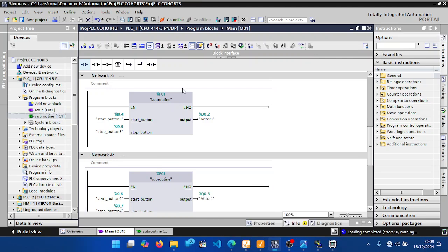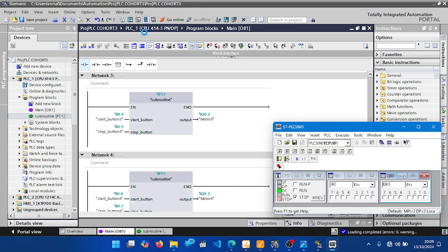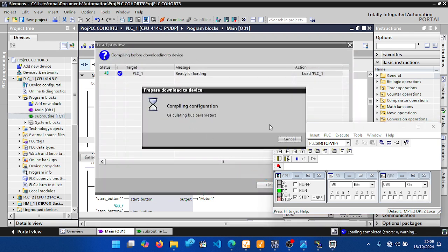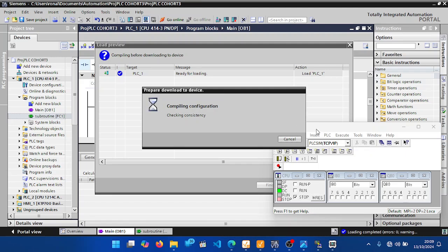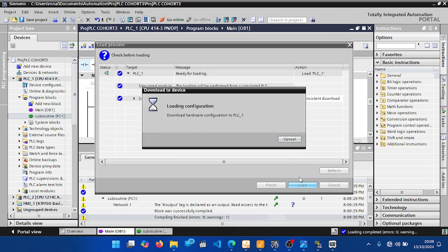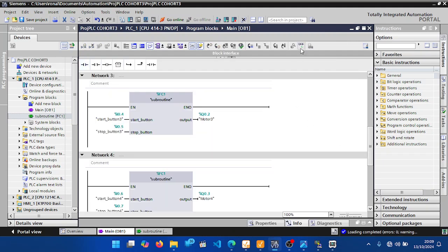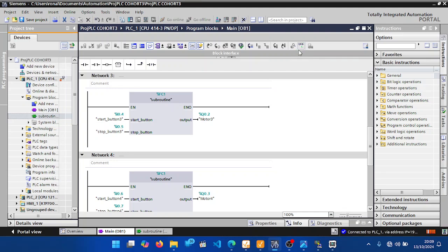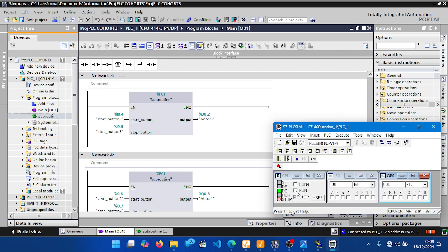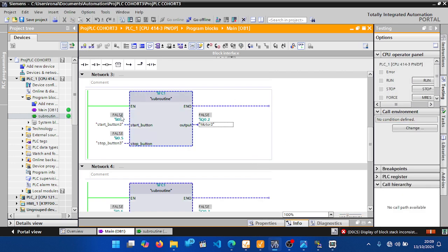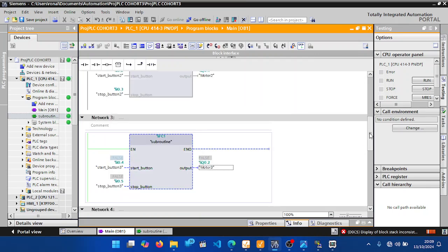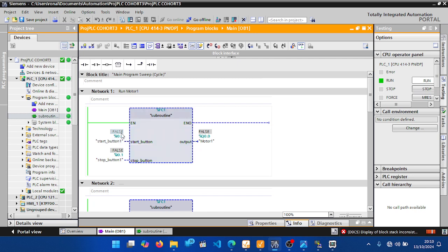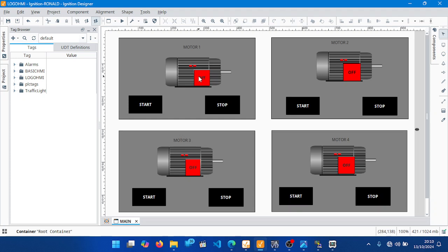After that, start the simulation. Compile and load the program, then go online. You can see all the subroutine blocks show false — the output of each block is false. The inputs are false because no start or stop push button has been pressed, and the motor status is false — all motors are off.